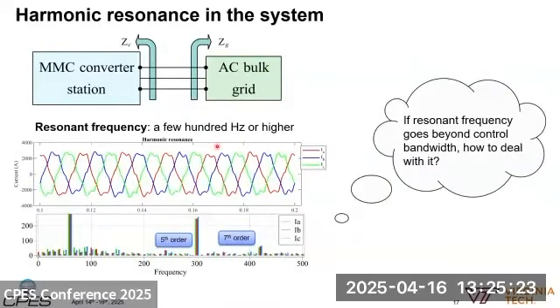Starting from this page, we're trying to deal with existing harmonics resonance in the system. This harmonics resonance is mainly caused by impedance interaction between the converter itself and the AC grid. Since the AC grid keeps changing and you don't have a complete idea of how it's composed, sometimes it appears that the resonance comes from nowhere.